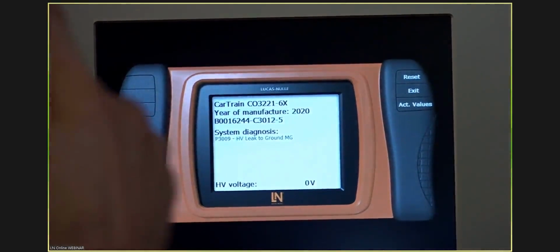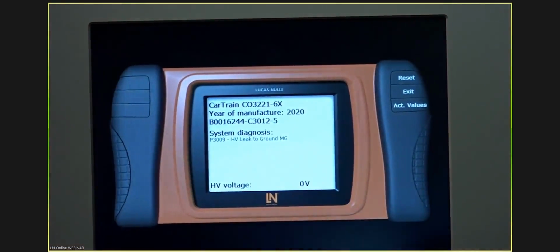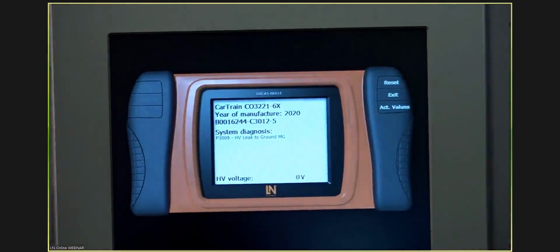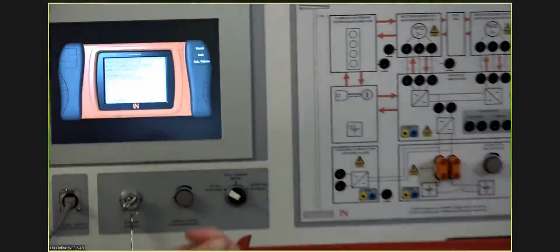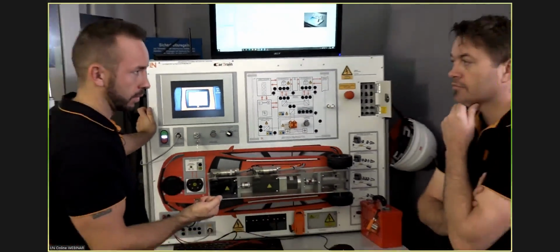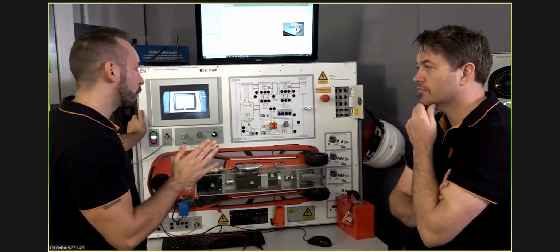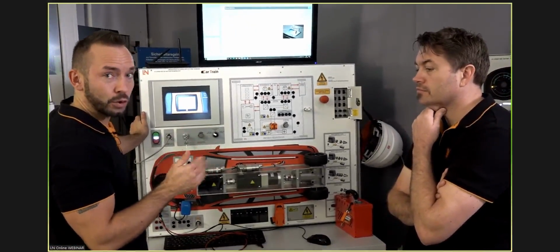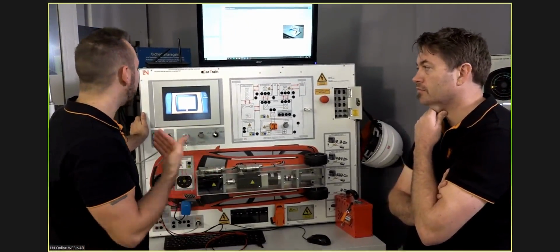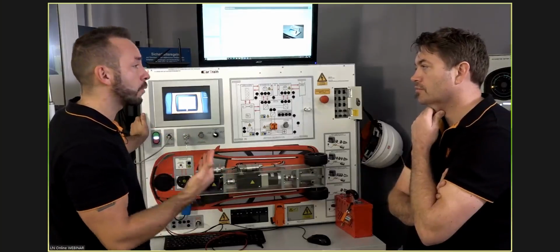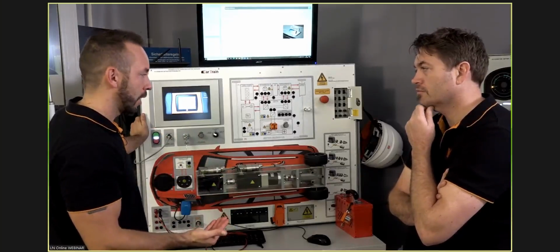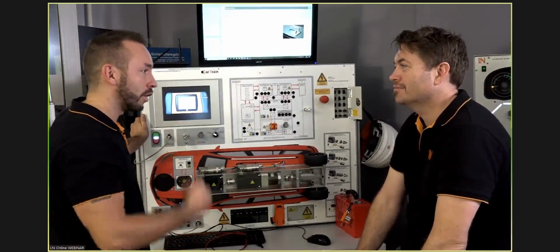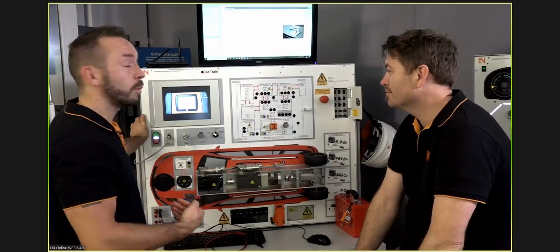First thought: what do we have to measure? When we're talking about insulation, we're talking about resistance, electrical resistance. There are a few traps that can happen if you use the wrong measurement tools, but at least we can agree we have to do a resistance measurement. And we all know that to do a resistance measurement, we have to make it voltage free.